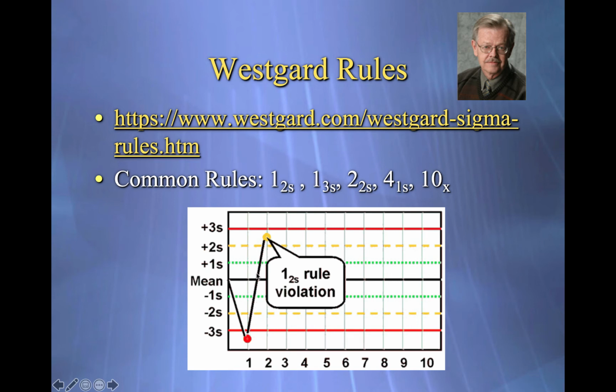I brought the thing back into control, but I still have one value out by 2 standard deviations. Let's say this is my low control. That may not mean you're failing your control, but it's a flag to watch that.